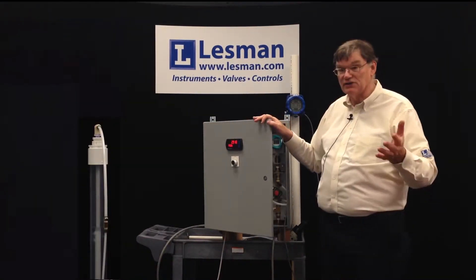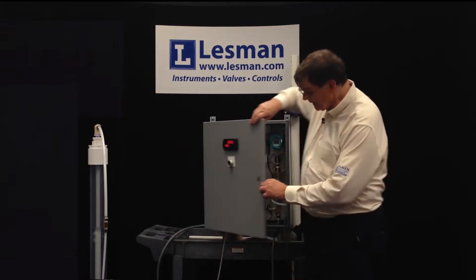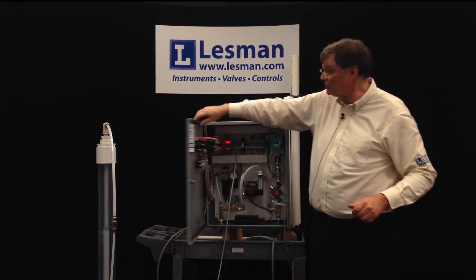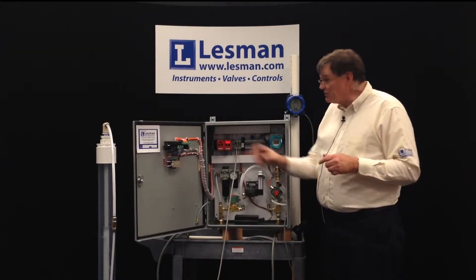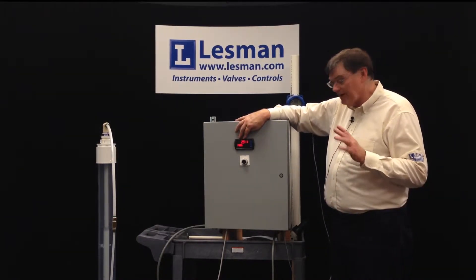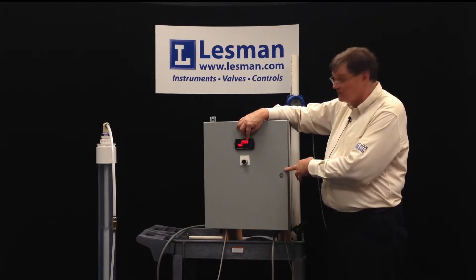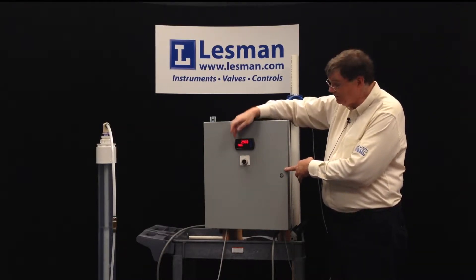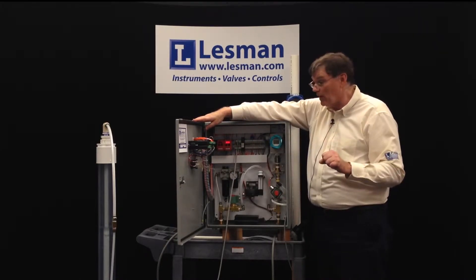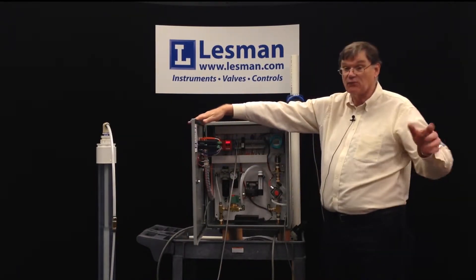The panel itself is conventional NEMA 4 construction, meaning it's weather tight — it has a big door gasket and a quarter-turn latch that secures it. The digital indicator is a conventional eighth DIN horizontal-mount precision digital meter. We've handled precision digital meters for 30 years and they're very reliable. The upper display shows the level or volume — the process variable — and the bottom shows the units. On the back there's wiring for two relays for control or alarm, plus a 4-20 mA analog retransmit signal that goes back to the control system.